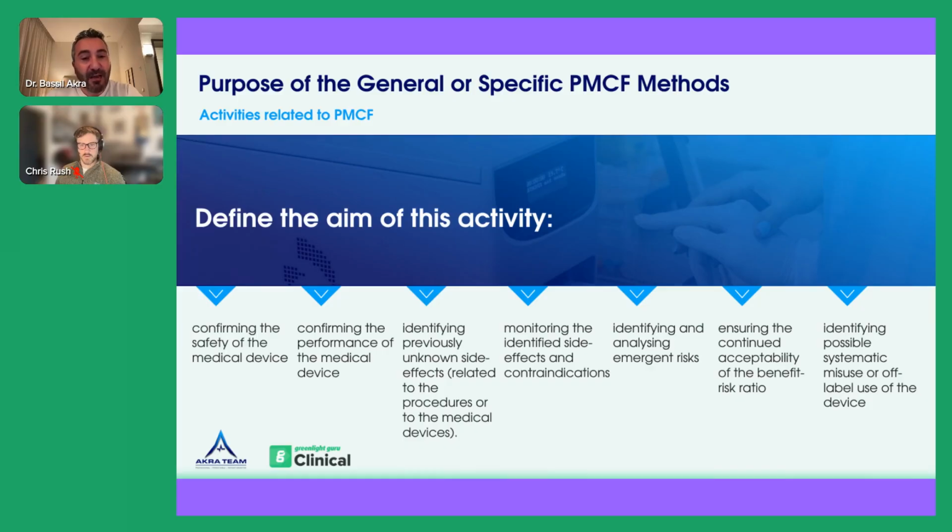In that PMCF plan, there are methodologies which are deemed general and some which are deemed specific. The specific ones are there for devices which require midterm and long-term data. For example, if you have a heart valve, you don't get that device on the market by having 10 or 15 years of clinical studies.